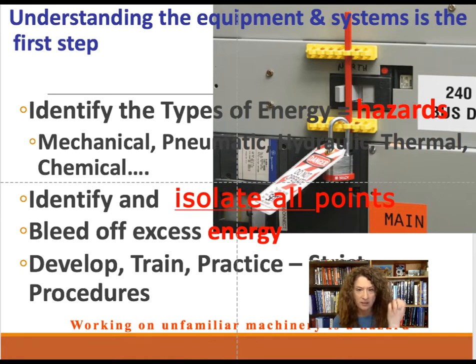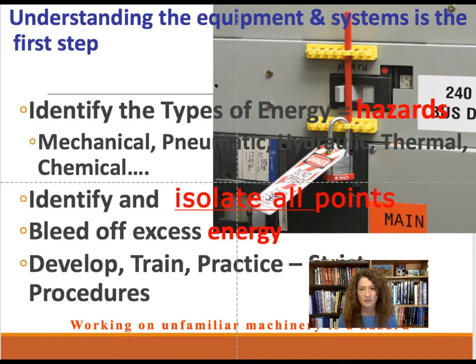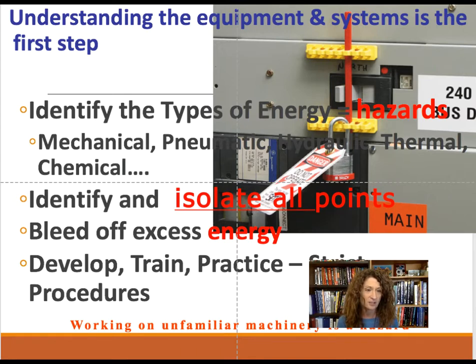You have to understand how energy can be released and what kind of energy could cause injury. Identify all the points where energy enters the system or can be released. This isn't just unplugging something — if there's built-up pressure or energy in a capacitor, you have to identify and bleed it off. Most workplaces have pre-written lockout-tagout procedures. Writing these SOPs and reviewing material safety data sheets are good tasks for people just getting into the industry.